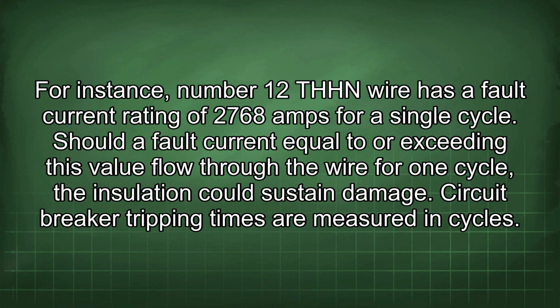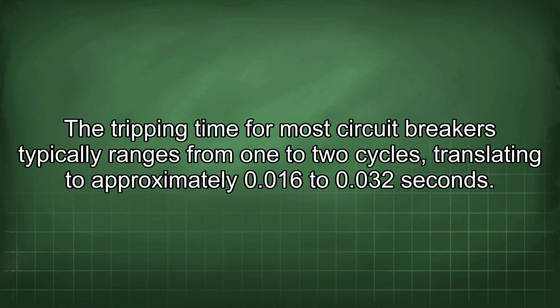For instance, number 12 THHN wire has a fault current rating of 2768 amps for a single cycle. Should a fault current equal to or exceeding this value flow through the wire for one cycle, the insulation could sustain damage. Circuit breaker tripping times are measured in cycles. The tripping time for most circuit breakers typically ranges from 1 to 2 cycles, translating to approximately 0.016 to 0.032 seconds.